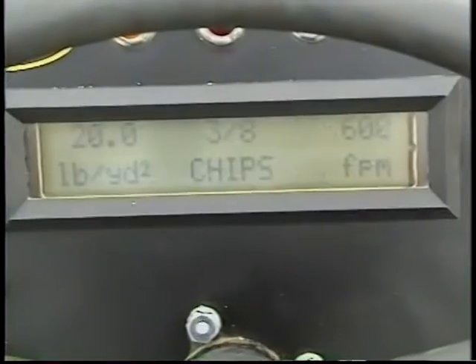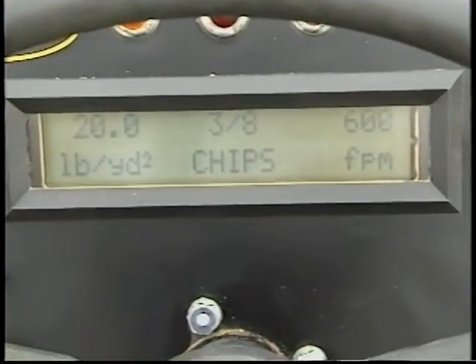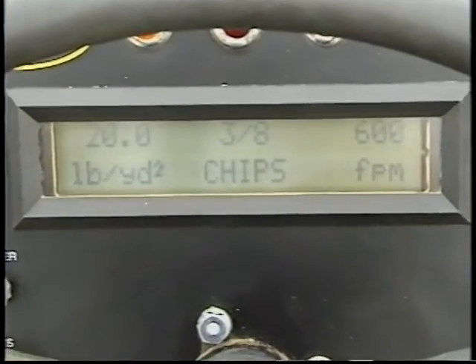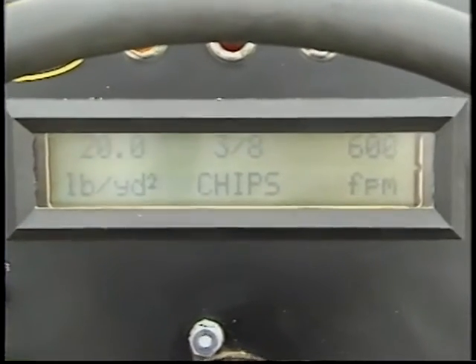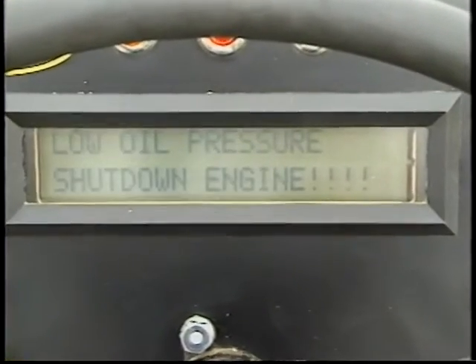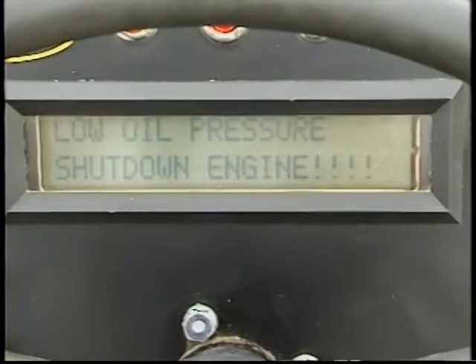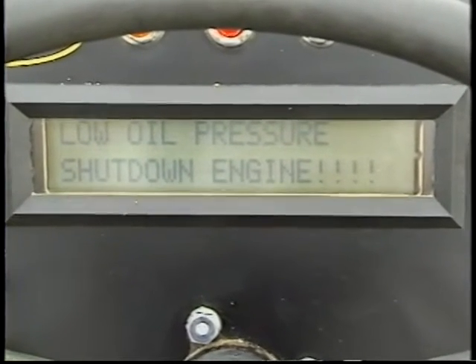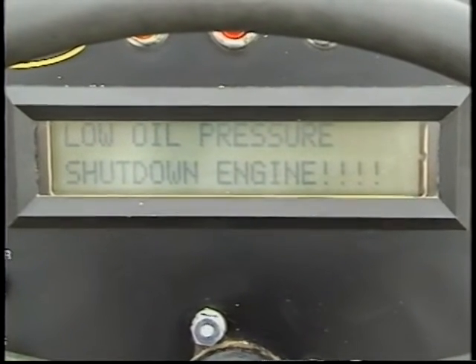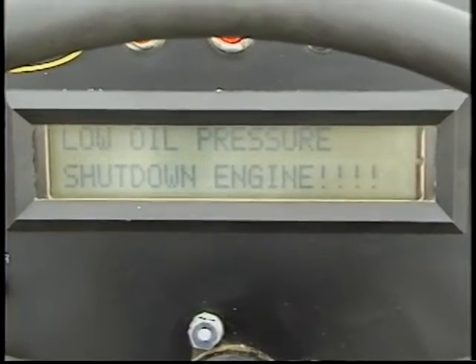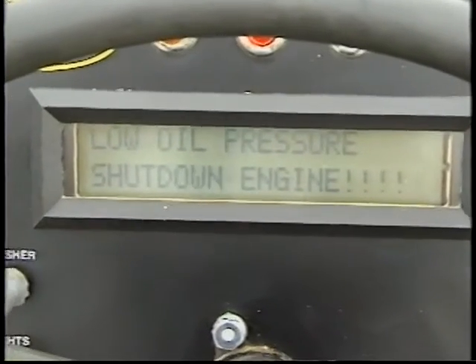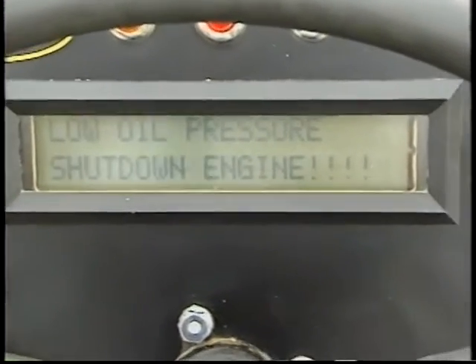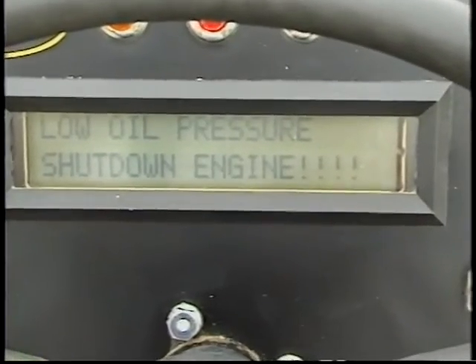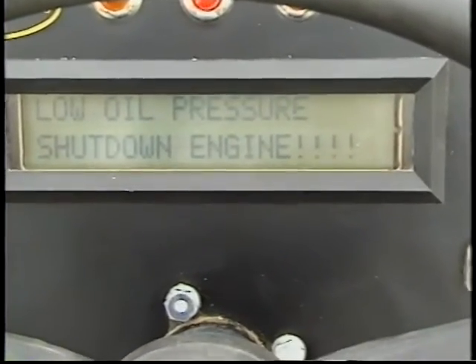A series of alarm functions are built into the computer. If an item sensed by the computer reaches its programmed alarm condition, the appropriate item will appear in the screen, regardless of what screen is currently displayed. In addition, an output is sent to the beeper and also to the warning light mounted on the upper part of the control box. The alarm points are as follows.